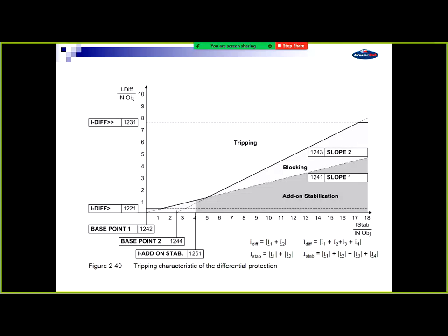This is what I was saying. You see the diff down the bottom, in the middle there, is just I1 plus I2, and the stabilised bit or bias diff or restraint, so it gets used different terminologies, but this is a Siemens one, they call it stabilised, is just I1 plus I2, whereas before that was divided by 2. But what you'll see is you get more current down the bottom, so that's an external fault will pull a lot of current through the transformer, so that stabilised current will get bigger.